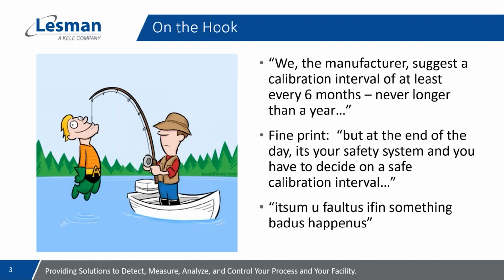The salesperson may have implied that calibration is minimized or eliminated because of some inherent stability of the design, or that the system prompts you to calibrate it, but nothing gets you off the hook. Manufacturers will always state that it is up to you, the end user, to confirm performance of the system, regardless of the technology used. Even if the engineering team is fully confident of the technology and design, the lawyers will always weave in a hedge to cover something the engineers may have not anticipated.